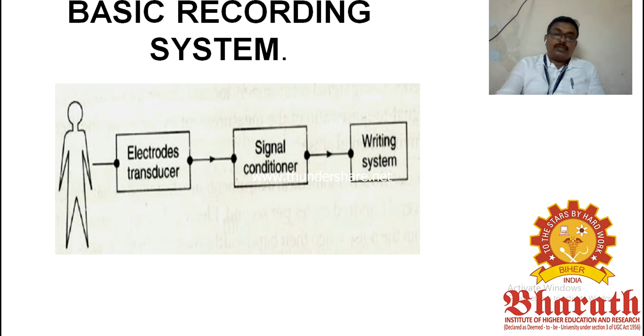So now the entire basic recording system: the measurand gives the biosignal, which is converted to an electrical signal, then in the signal conditioner box the obtained electrical signal is strengthened, right, and you get a noise free signal which is compatible with the writing or recording system. That is what is explained here. Signal conditioners record any one of the physical or bioelectric events on the same writing channel. The writing systems, which are available in many forms, constitute the key portion of the recording instrument. The commonly used writing systems are the galvanometer type pen recorder and the potentiometric type recorders, right.